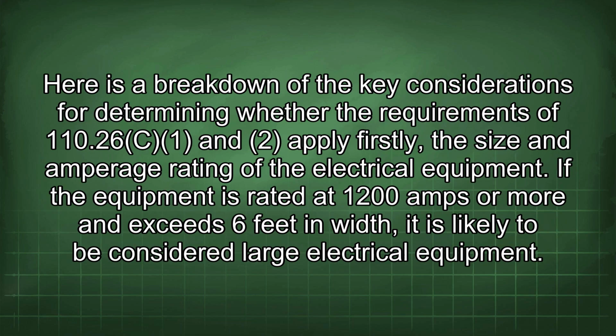Here is a breakdown of the key considerations for determining whether the requirements of 110.26(C)(1) and (2) apply. Firstly, the size and amperage rating of the electrical equipment. If the equipment is rated at 1200 amps or more and exceeds 6 feet in width, it is likely to be considered large electrical equipment.